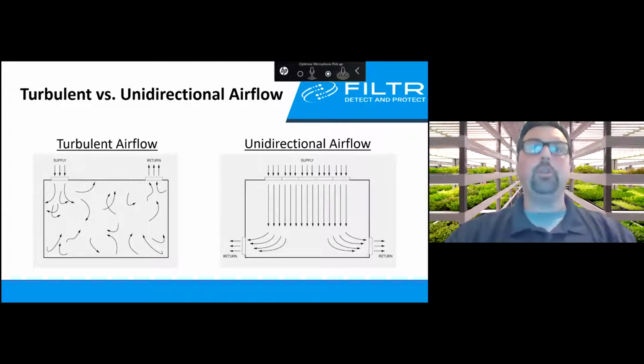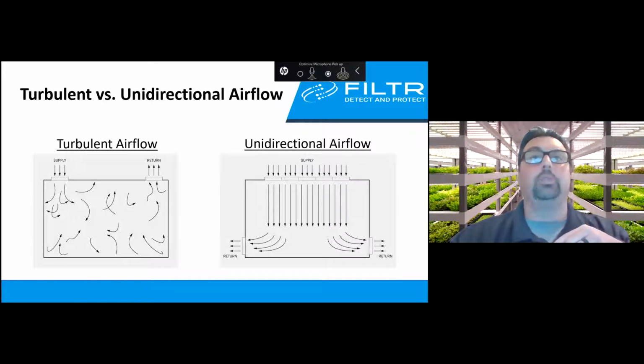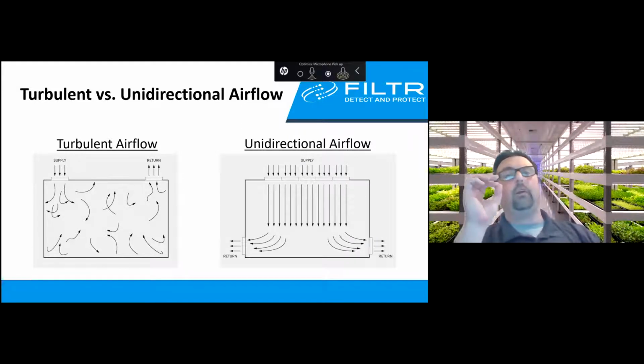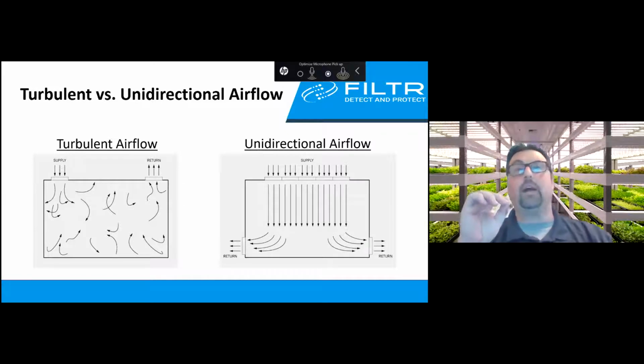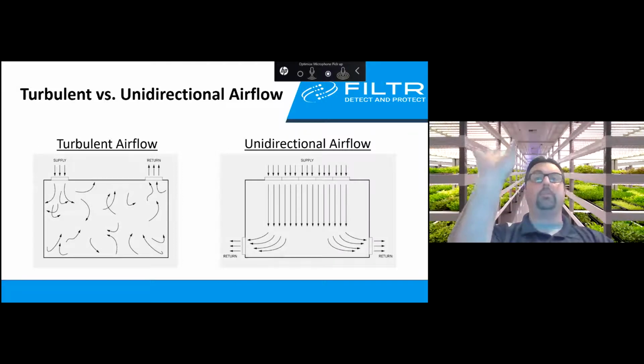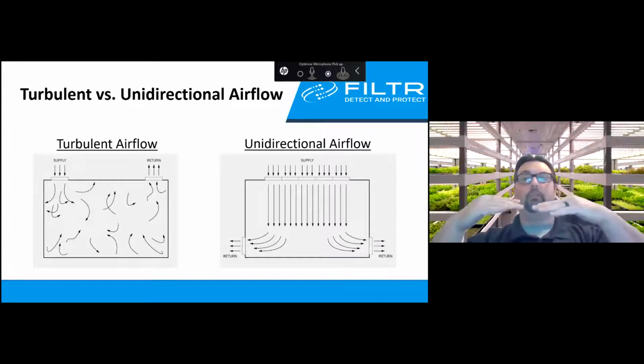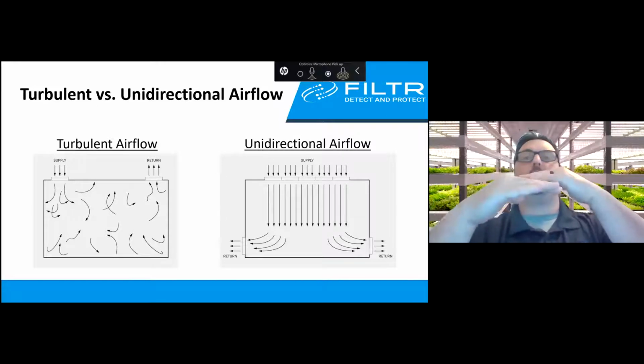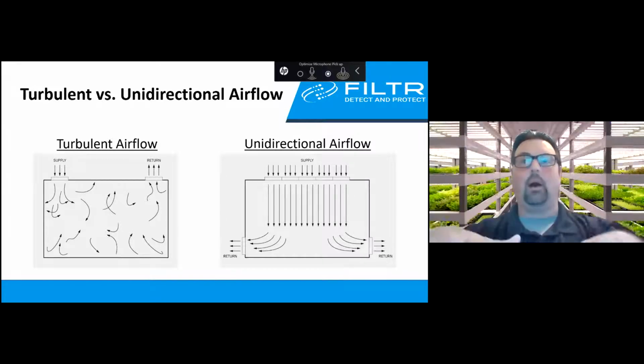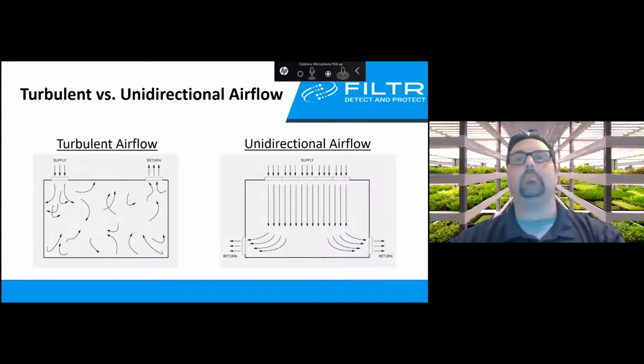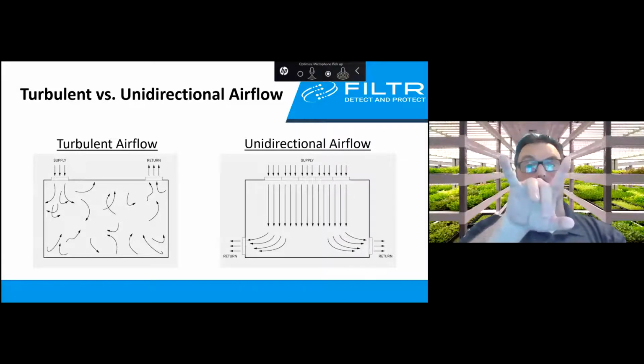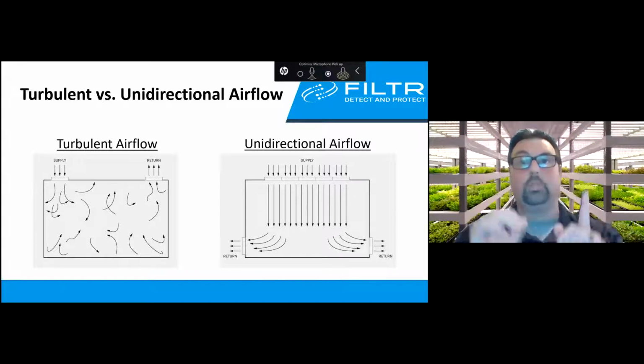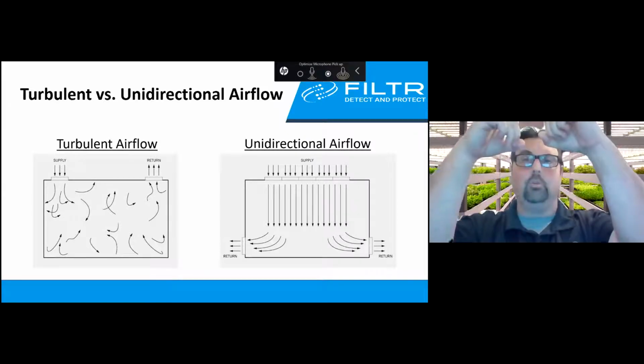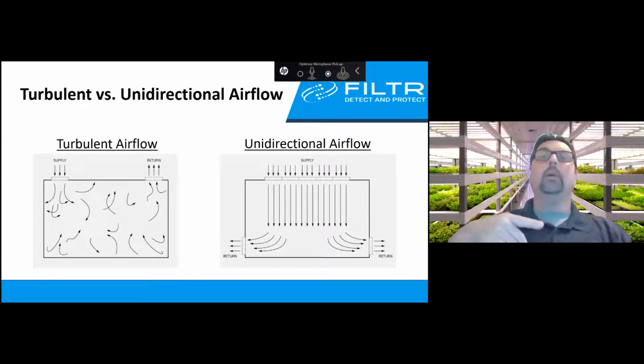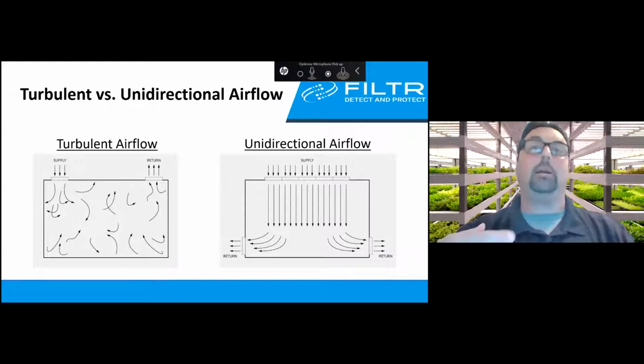On the other side is what's called unidirectional airflow. This is the kind used in pharmaceutical clean room manufacturing. They set up a grid on the ceiling with downward-flowing fans, and the air pressure in the entire room is stabilized, coming down all at the same time and speed. That air goes into returns at the bottom of the floors, with a dead wall space between the outside walls, and circulates back up to the top of the room and down again. So they're trying to circulate as much of their own air as possible.